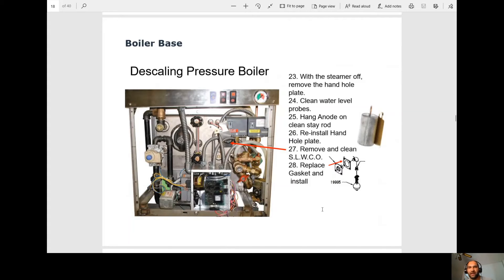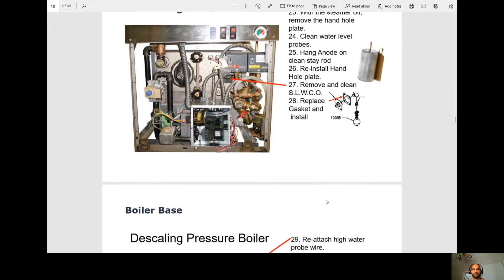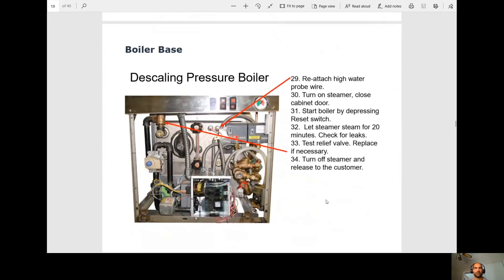Now with the steamer off, remove the hand hole plate. You're going to clean the water level probes. You're going to hang the anode and clean stay rod. You're going to reinstall the hand hole plate. You're going to remove and clean the secondary low water cutoff, which is located right here. And then replace the gasket. At this point, you're going to reattach the high water probe. Because we don't want it to overfill, obviously. You're going to turn on the steamer. Close the cabinet door. You're going to start the boiler.